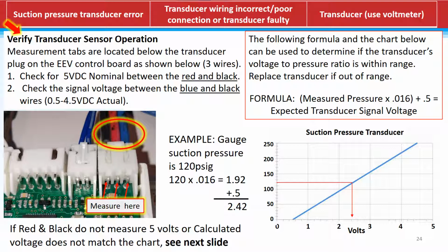Remember to set your meter to DC if your meter doesn't automatically adjust. With 5 volts DC here and the system running, you need to check the signal between blue and black, and you're looking for a reading between 0.5 and 4.5.